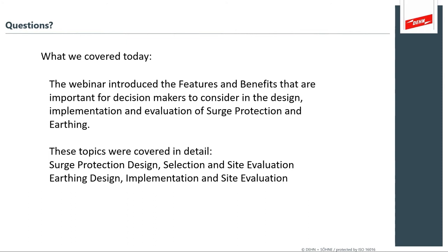So the risk assessment will tell you the measures you need to put in place, and that helps you pick the surge protection device and the energy it needs to withstand. This is one of the advantages of IEC methods: it allows you to select higher and higher levels of risk control for things like a hospital with explosive environment, oxygen atmospheres full of people that are very difficult to evacuate, where you have a high risk of fire and a high risk of life threat.